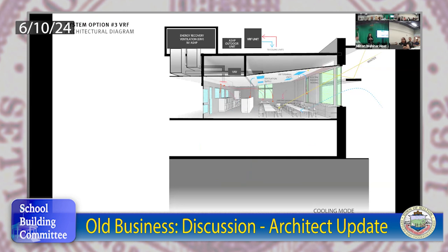So we talked about acoustics from the overhead versus displacement, and just the nature of overhead, it is louder because of the velocity. And specifically if you're doing overhead with a VRF, that's a little bit louder as well, because there are moving mechanical motors in all of those ancillary units in the ceiling. Whereas if you did it overhead with, say, a ground source system, that overhead would be a little bit noisier because you're having air come down at high velocity, but the actual grill looks like there's no moving part, there's no mechanical unit up there. But with a VRF, you have essentially a mechanical component in the ceiling that has motors.